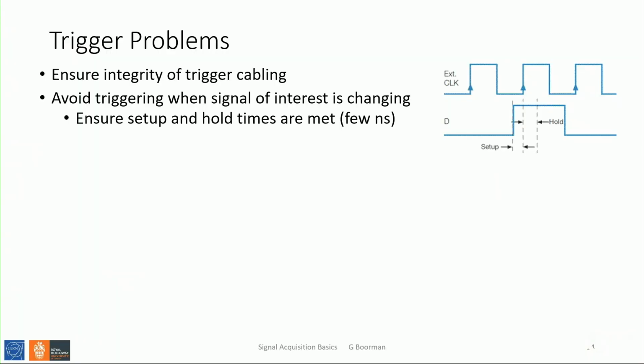So the trigger problems. First of all, make sure your cabling is correct. You've got all the little toys to play with here. And ensure your setup and hold times are met. So if you've got a trigger at the right time for a particular signal, make sure your trigger actually comes in when you need it, not slightly delayed. You'll find setup and hold times in the data sheets of all of the DAQ devices. So if I want to look at, say, this edge on a clock here, I need to make sure that my trigger comes in sufficiently before it.